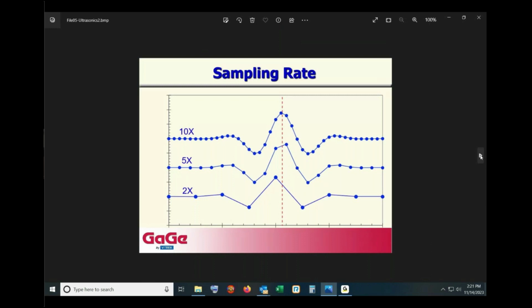The first thing I'm going to show you is the advantage of sampling rate. So the two banner specifications of a digitizer are its sampling rate and its resolution. And the sampling rate is important in ultrasonics to the extent that it allows us to determine the position in time of ultrasonic echoes. So here I've shown a typical ultrasonic echo.